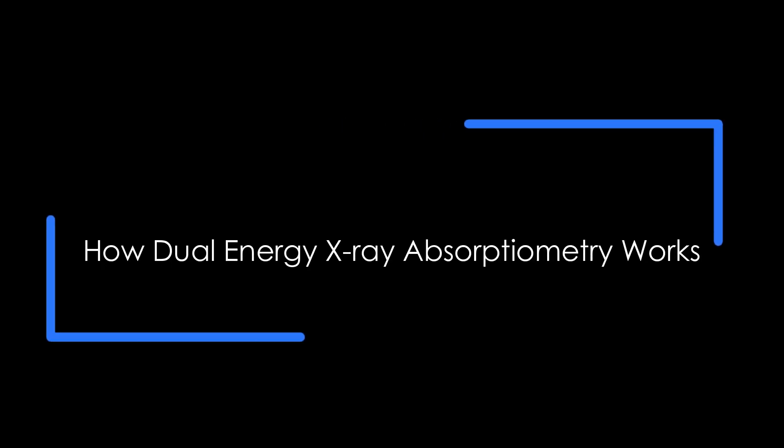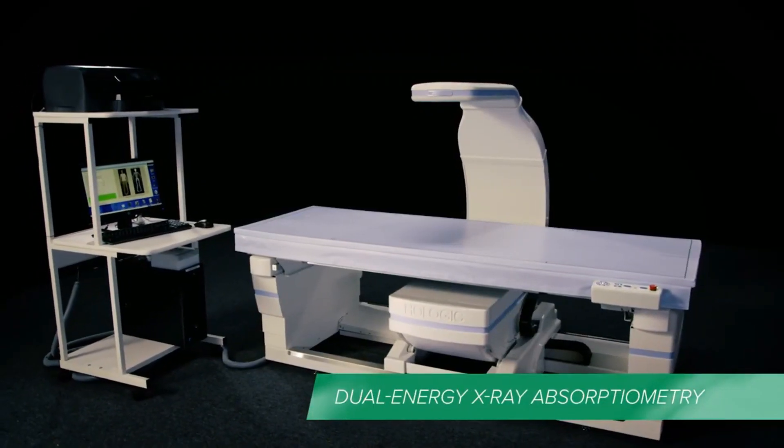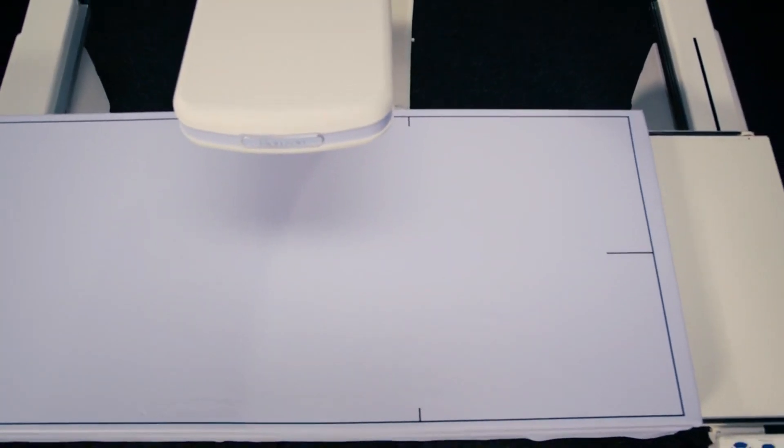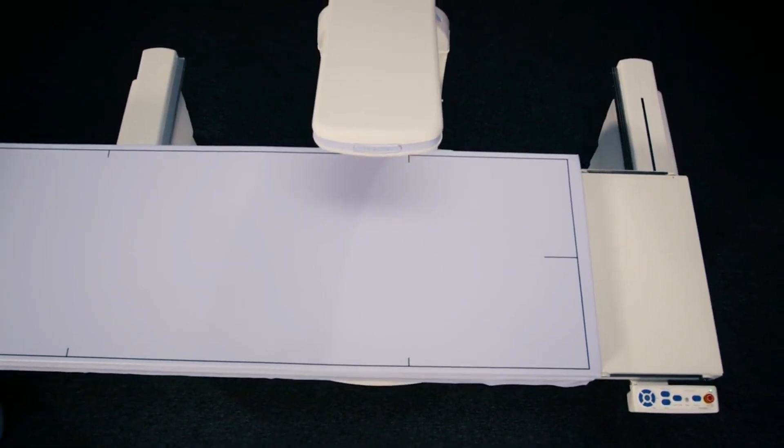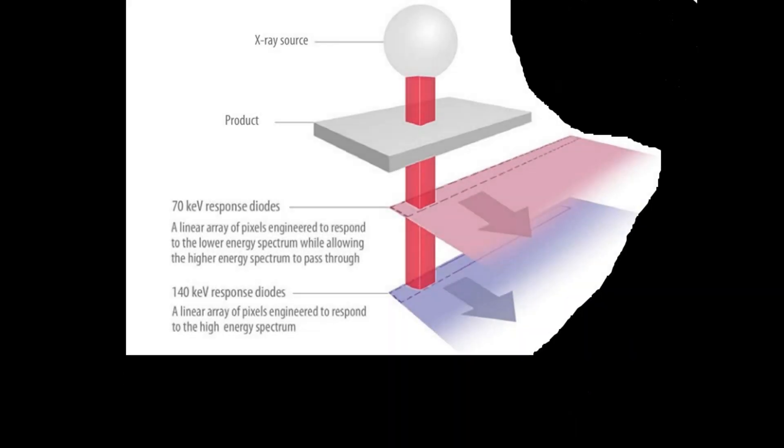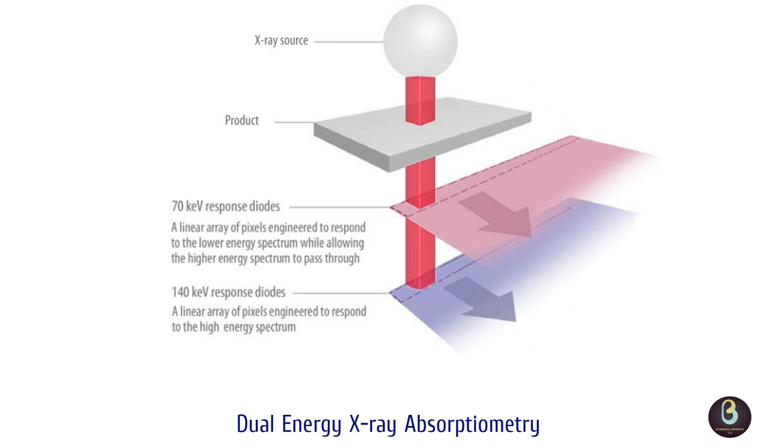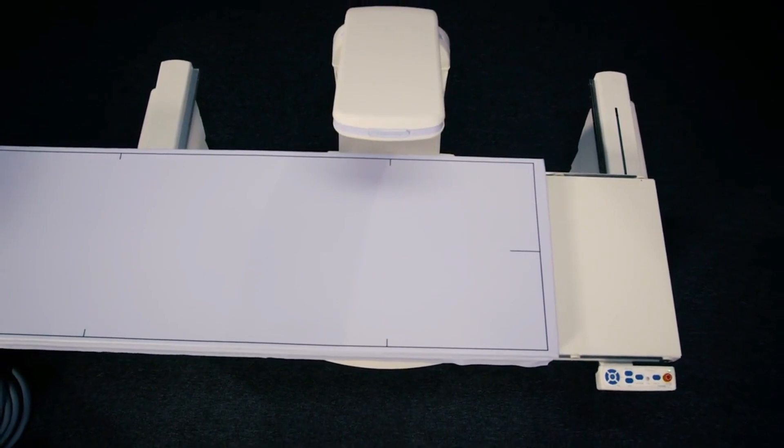How dual-energy x-ray absorptiometry works. DXA works by measuring the absorbency of two x-ray energy spectra by the product. Two linear scanning arrays of pixels, each sensitive to a different range of the x-ray spectrum, detect x-ray passing through the product, producing one dimension in the resulting images. Successive scans of product moving through the scanner produce the other dimension.